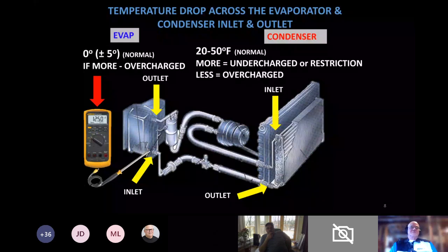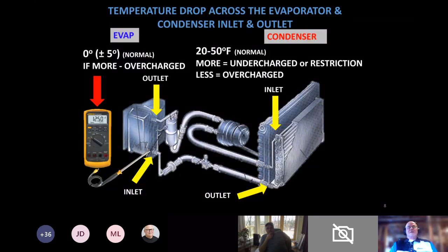In order to do that, I suggest not using an infrared thermometer. And the reason for that is if you shine an infrared thermometer on the wall, you'll usually see a target, red dots of a target that's usually 4 to 6 inches in diameter and does not give you an accurate indication of one particular point, which is what you want to measure when you're doing this test.